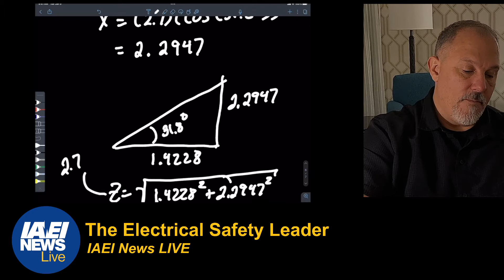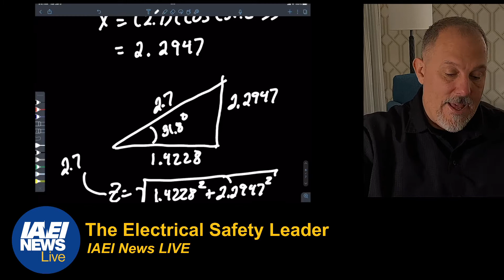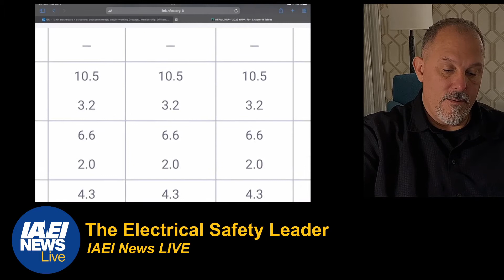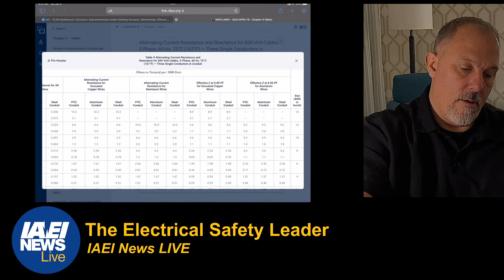And this is 2.7. So now you've calculated the resistance and the reactance, the power factor angle, and the impedance. That aligns with what is right here as your effective Z at 0.85 power factor. They are providing you enough information for you to draw that triangle.